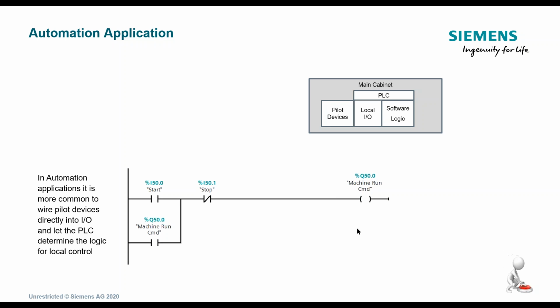Now the reason I'm bringing this up is that I'm going to show that this software is moving to the field in just a minute, and you'll understand a little bit further. But keep in mind about reducing logic in the PLC or the controller. There might be a run permissive about a remote mode, and so forth and so on.